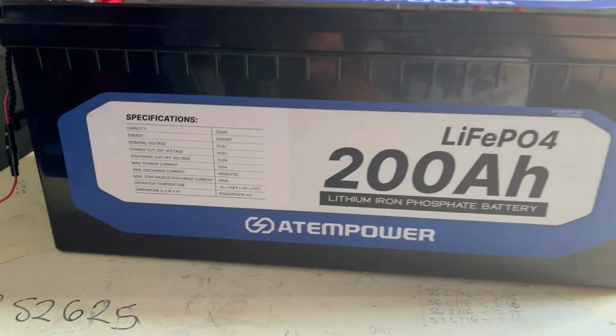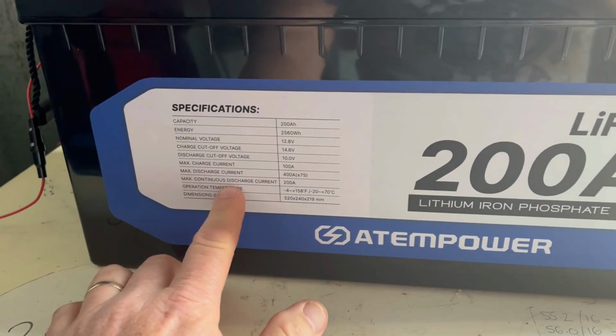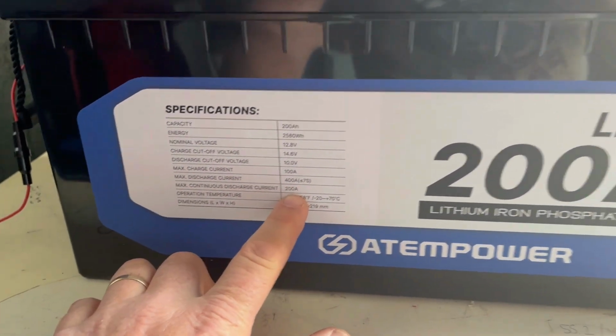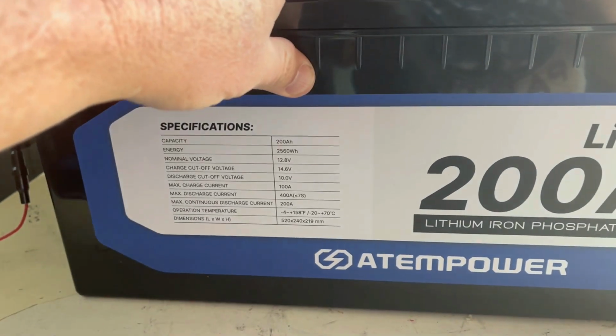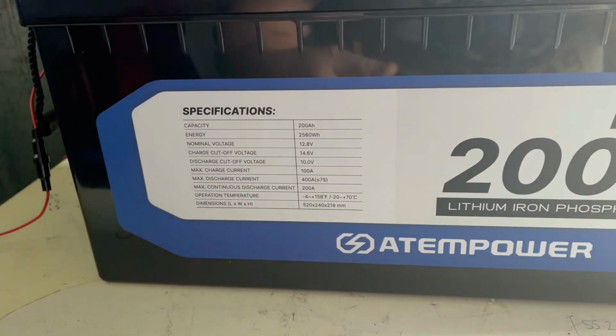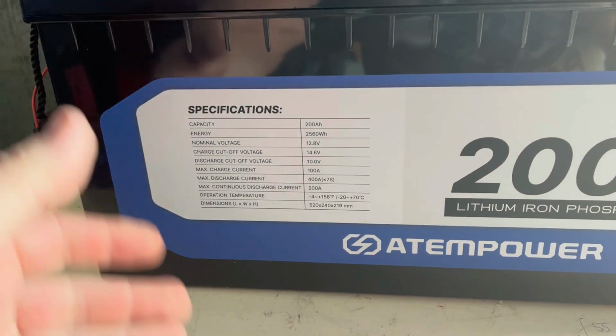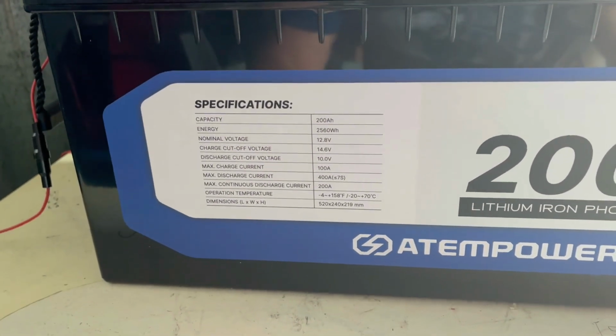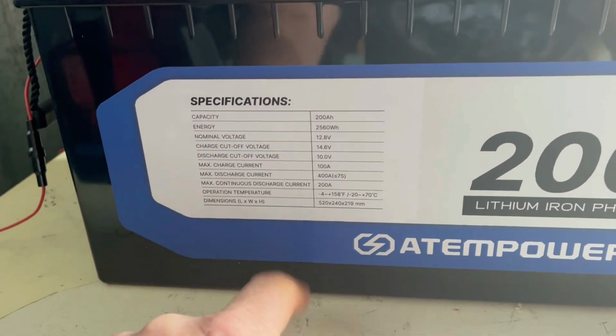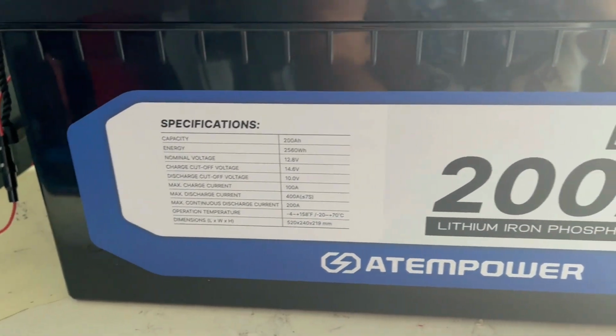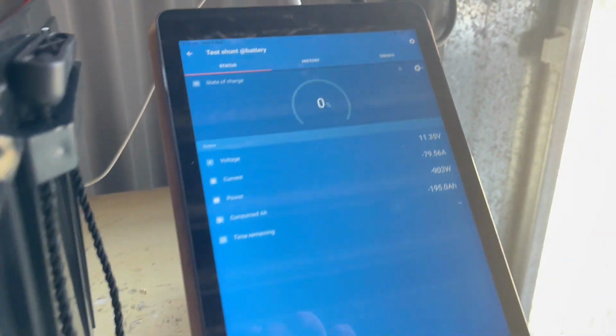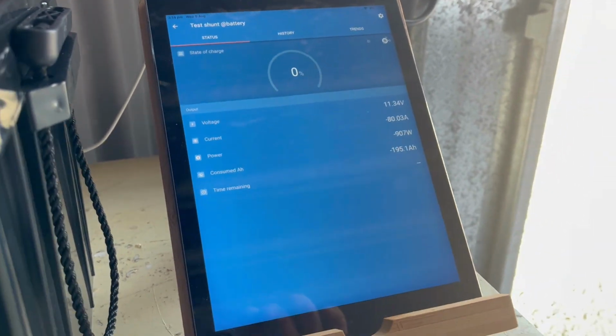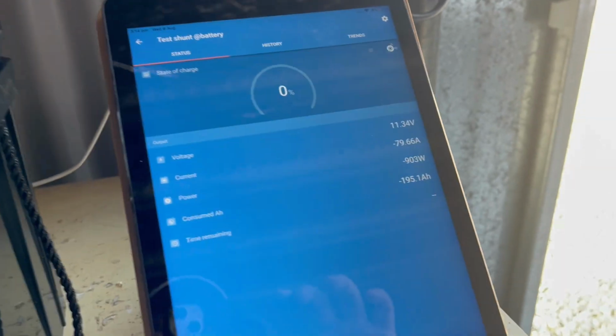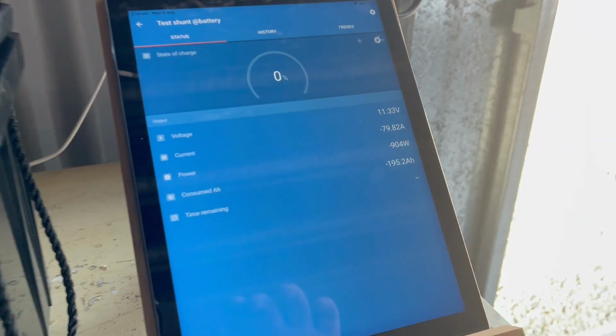Terminals seem okay. Maximum continuous discharge current is 200 amps on this battery. So what I might do is charge it back up again, let it sit there and absorb, let it do what it needs to do, and then do a hard discharge on it at maybe 150 amps instead of the 80 it's come up to now. Obviously the amps go up as the voltage comes down, so let's see what we get to.